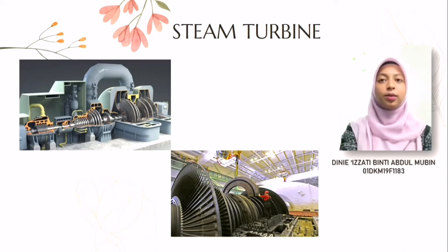Extracting type turbines are common in all applications. In an extracting type turbine, steam is released from various stages of the turbine and used for industrial process needs or sent to boiler feed water heaters to improve overall cycle efficiency. Induction turbines introduce low-pressure steam at an intermediate stage to produce additional power.